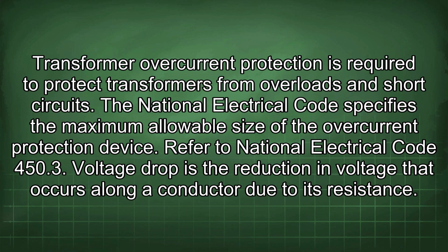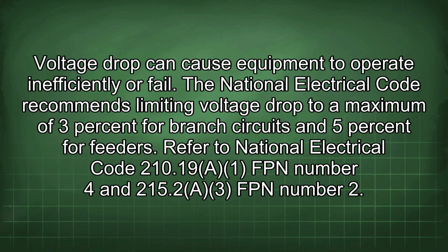Voltage drop is the reduction in voltage that occurs along a conductor due to its resistance. Voltage drop can cause equipment to operate inefficiently or fail. The National Electrical Code recommends limiting voltage drop to a maximum of 3% for branch circuits and 5% for feeders. Refer to National Electrical Code 210.19(A) FPN number 4 and 215.2(A) FPN number 2.